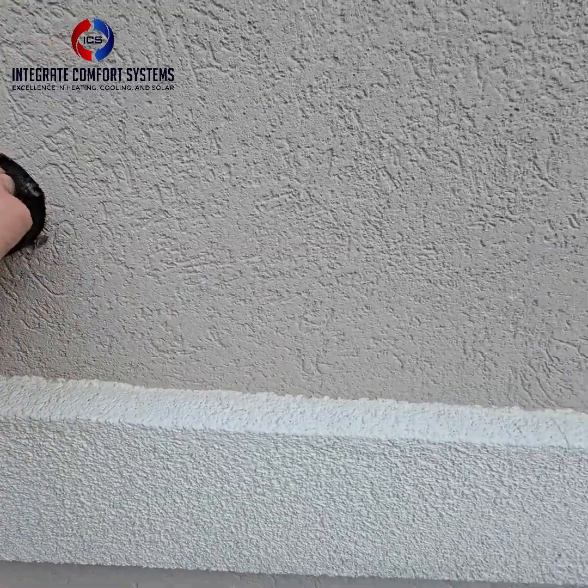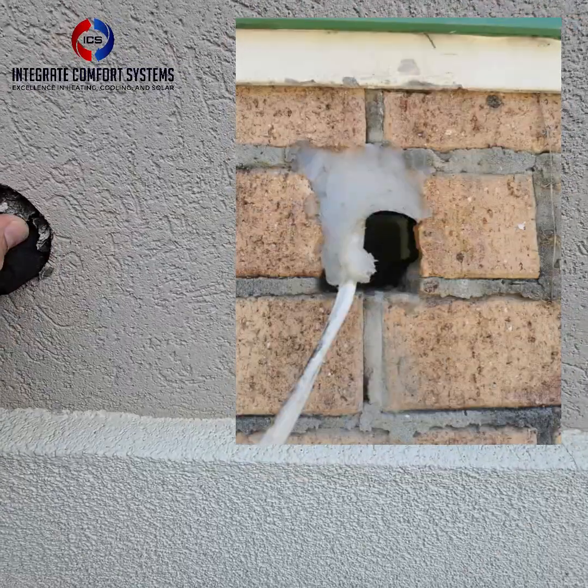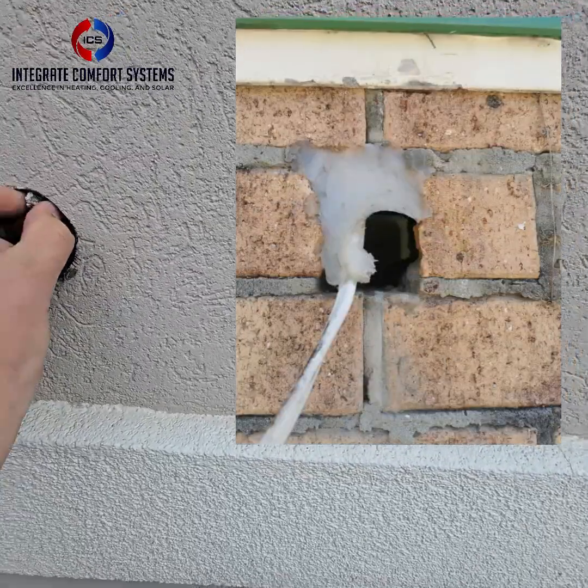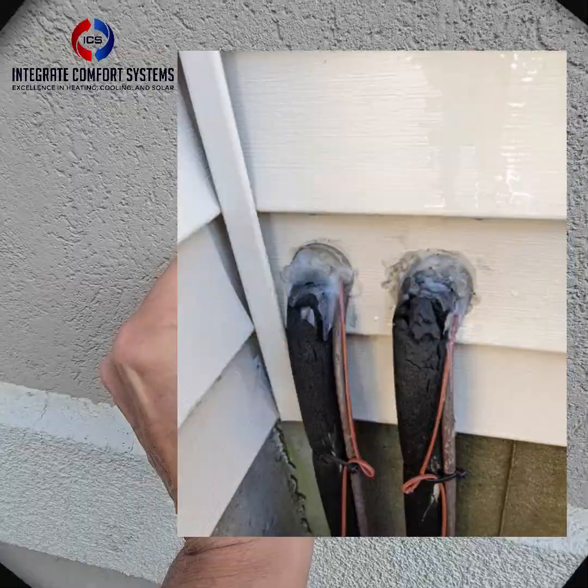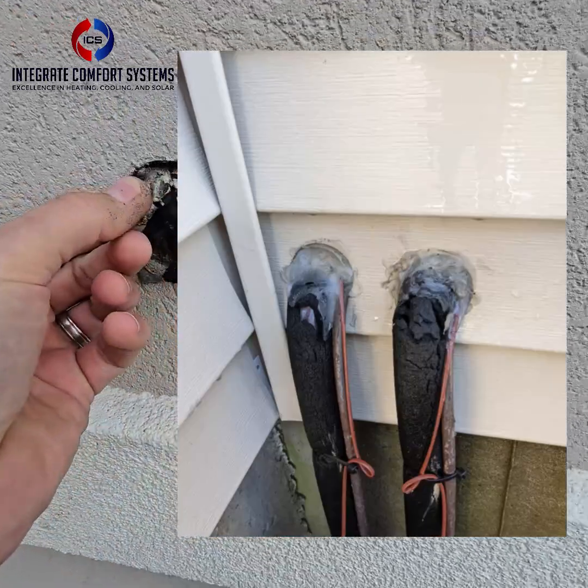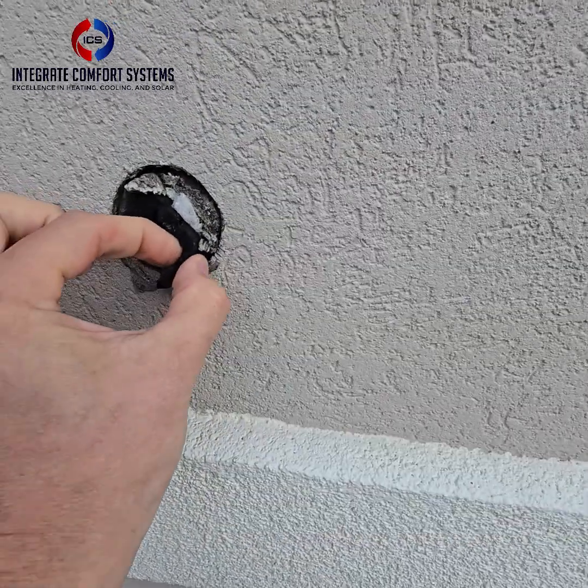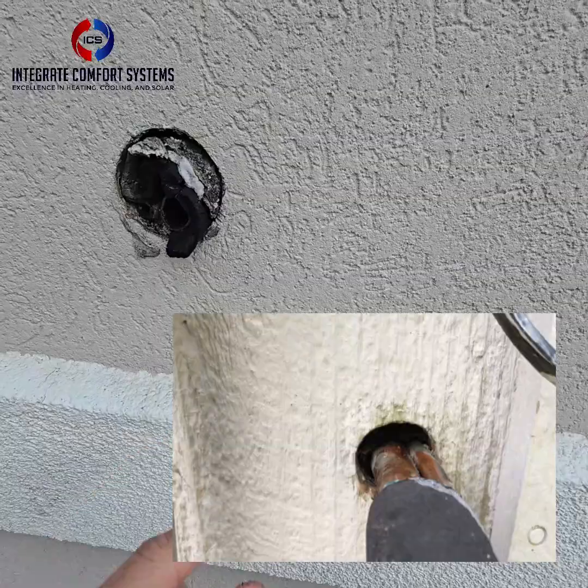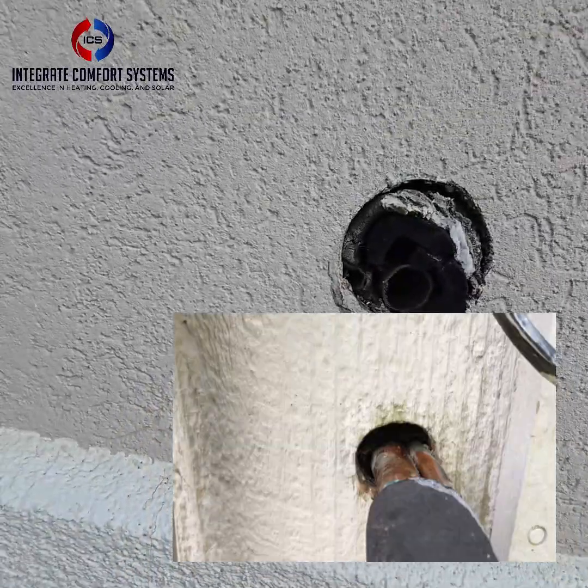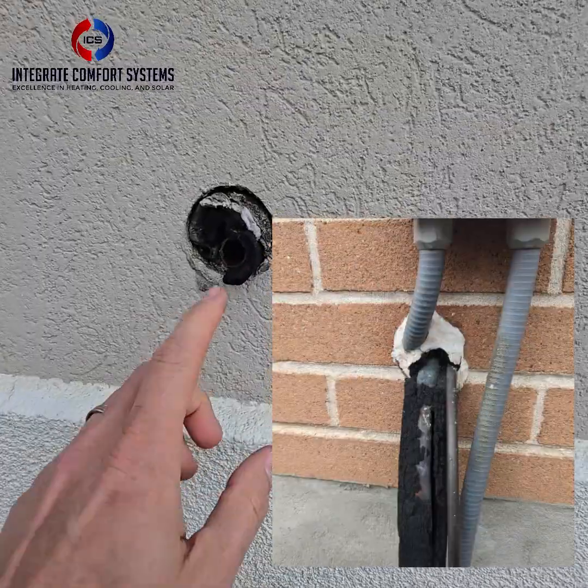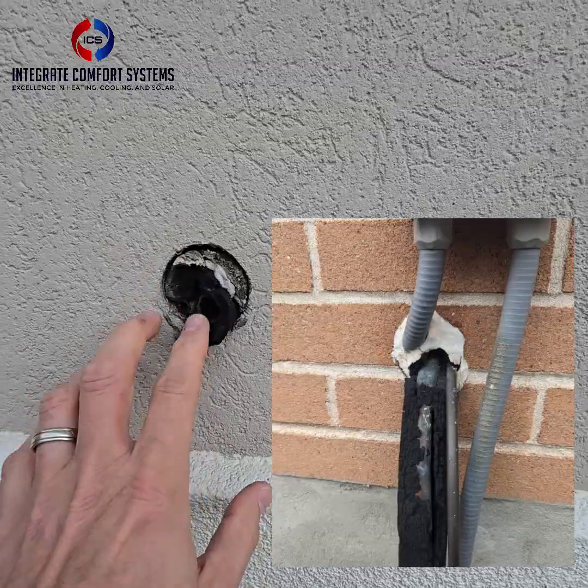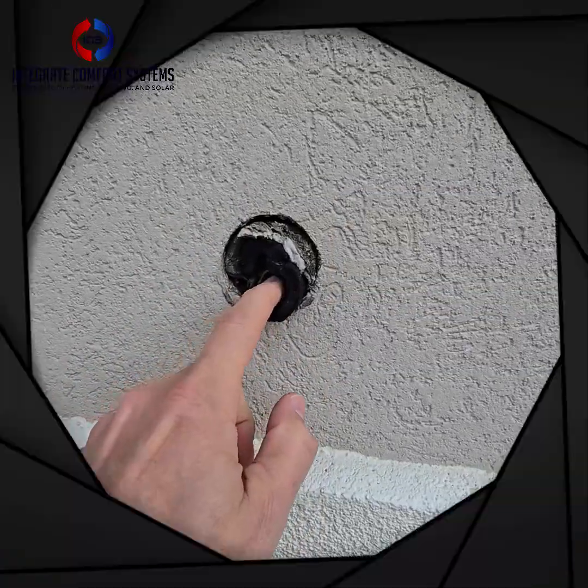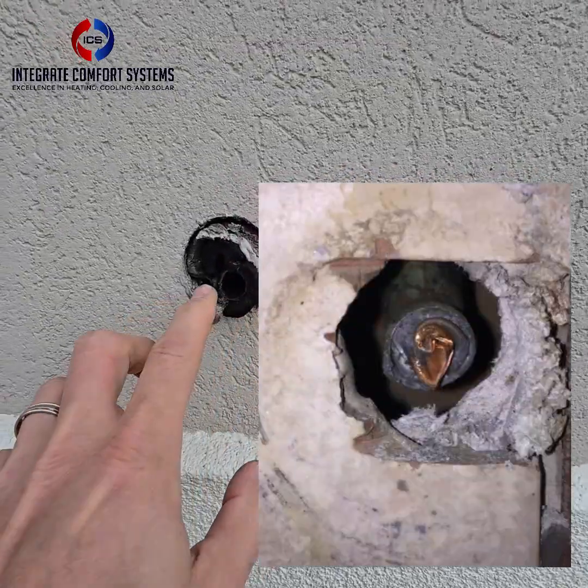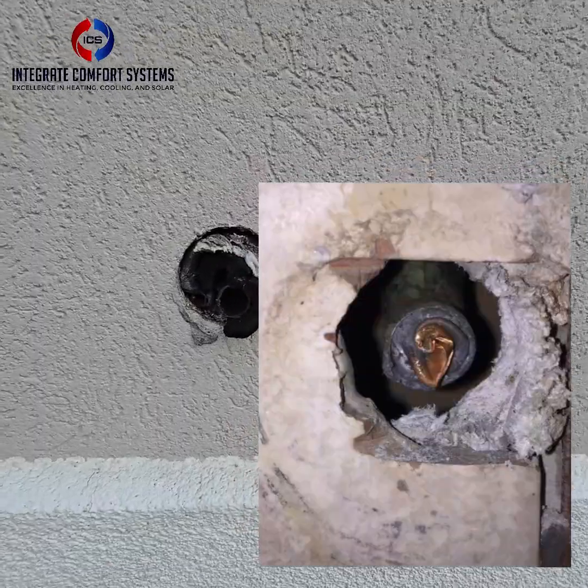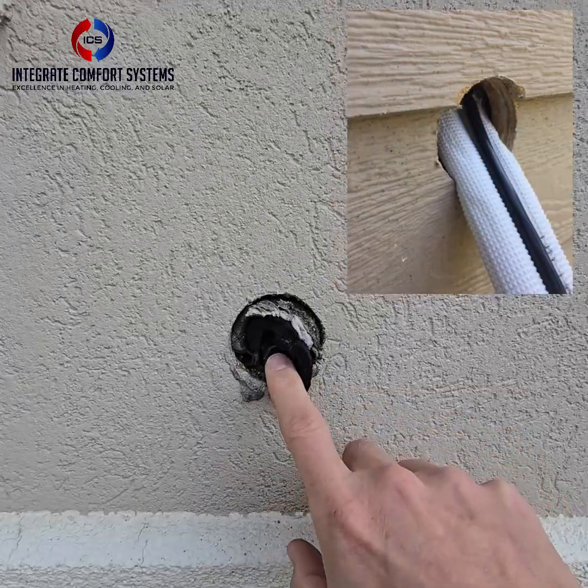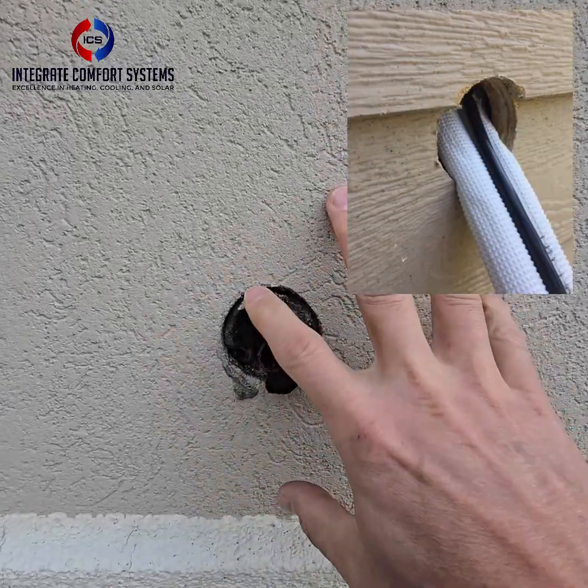and then they try to silicone, or somehow seal, which, you've got remnants of this stuff right here, which of course over time fails, but also you're sealing up against a soft insulation surface. But the bigger problem that we have here is that in a lot of these situations, now this is stucco, so it's masonry, we have copper pipes that are touching concrete, or some sort of concrete, but even if they're not touching concrete, they're touching some kind of structure.